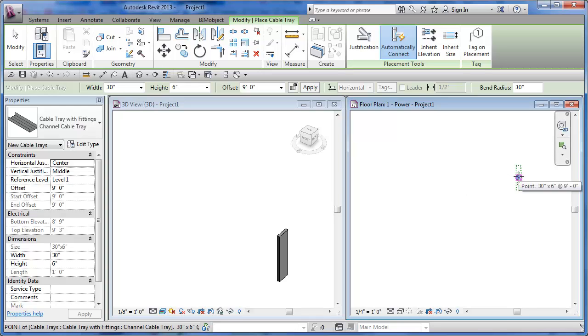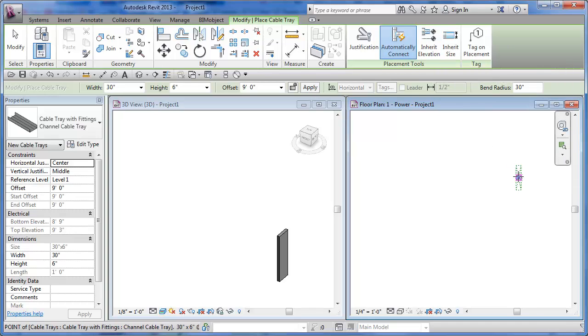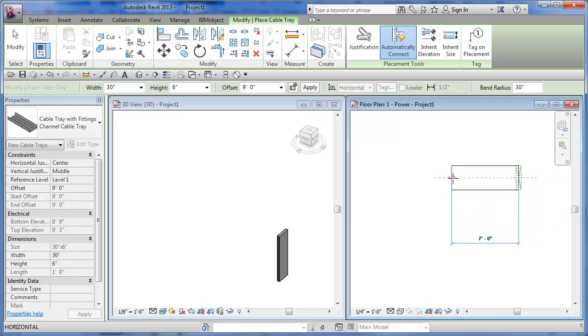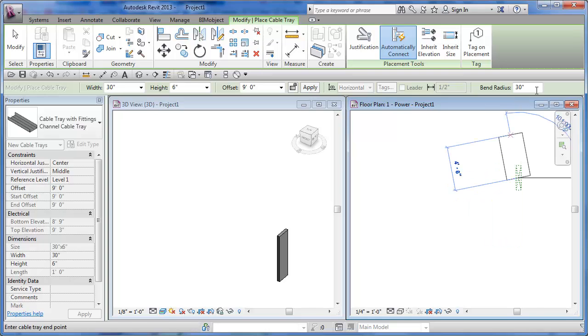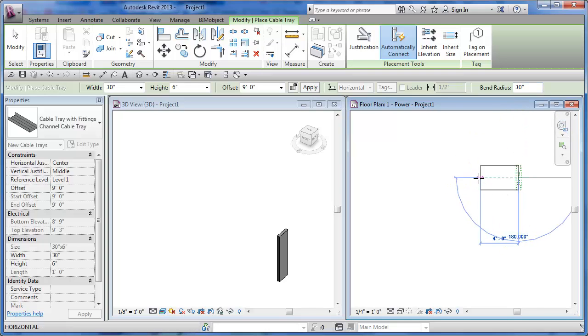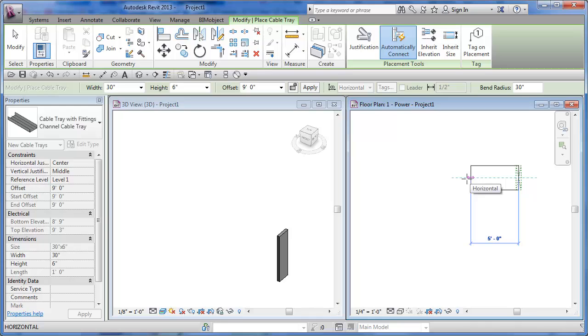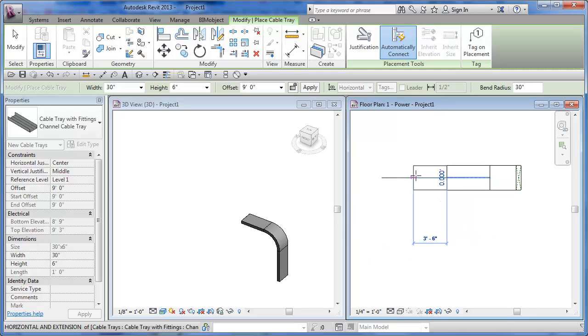Now I can hover over here — I don't necessarily have to say 'inherit elevation' — I pick on there and off I go. If I plan on going vertically again, this is where you really have to provide a lot of space, because you need enough room for a 30-inch radius bend, then a section of cable tray, then another 30-inch space. So it's better to go generously big. You can see it draws that bend in.